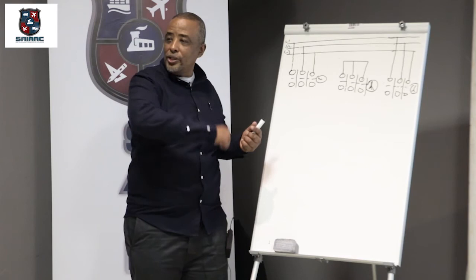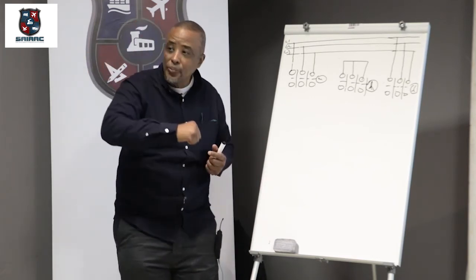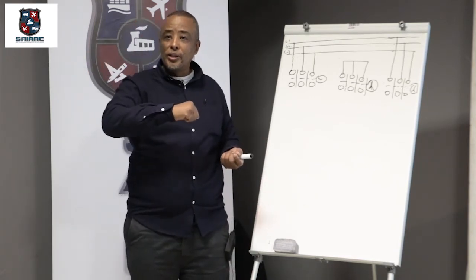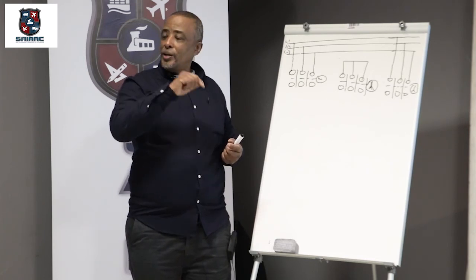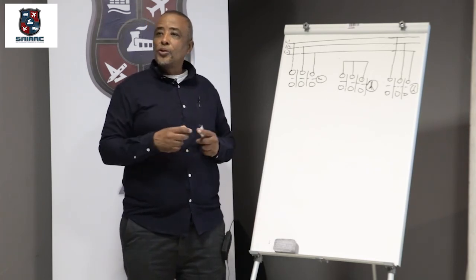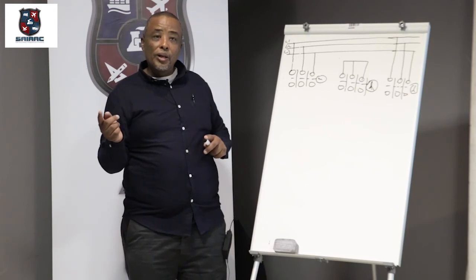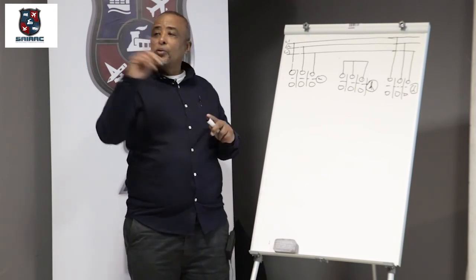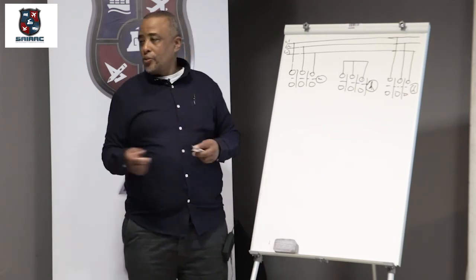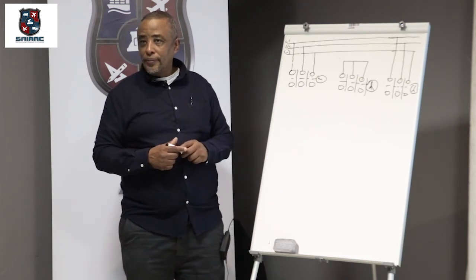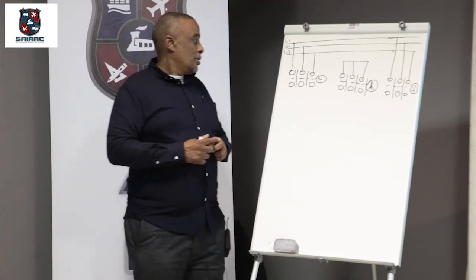They removed the operator from switching. Maybe he falls asleep and he has it running too long in star. And so they introduced a timer, where a timer automatically will switch it in, the motor will start in star, and then a timer will disconnect it from star and switch it over to delta. Okay. All right.